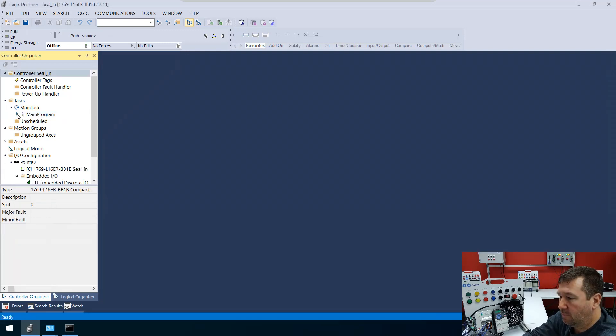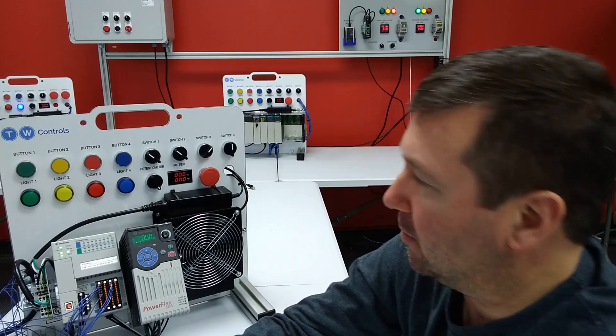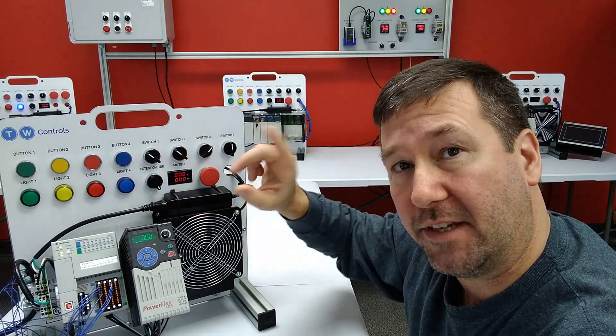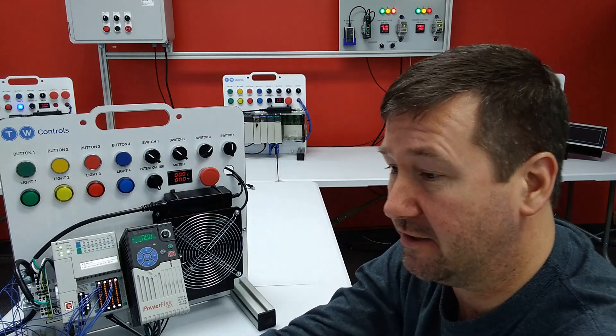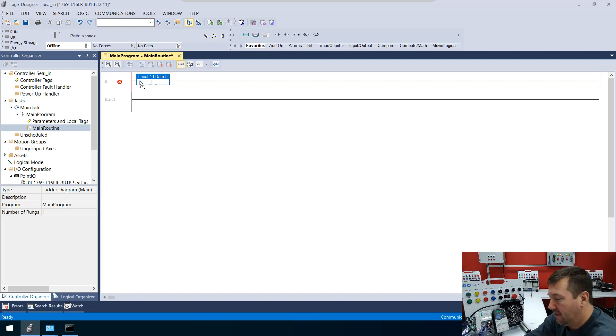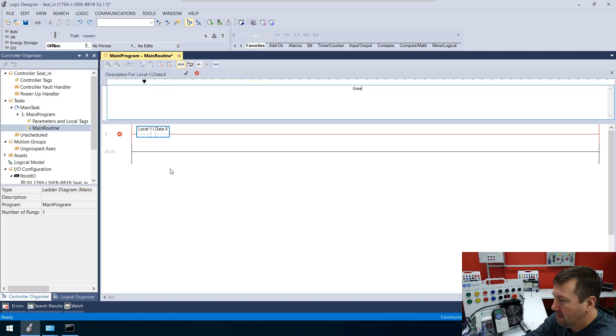Let's open up our main program and then our main routine, and let's drag down an examine-on instruction. We're going to be looking for the green button, which we have wired to input zero. This trainer is still wired for the getting started guide we did earlier in this series. So that's going to be local:1:I.data.0. Let's add a description — right click and go to edit main operand description, or simply hit Control+D. And that is our green button.